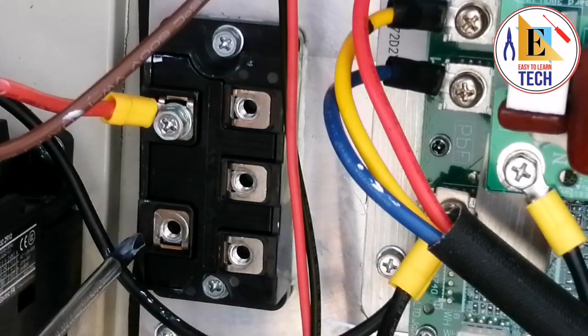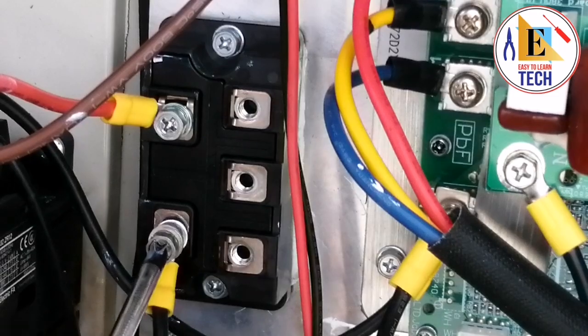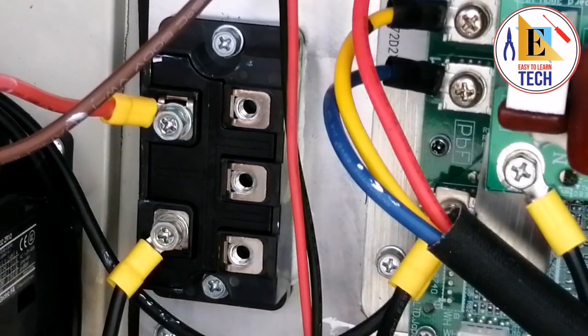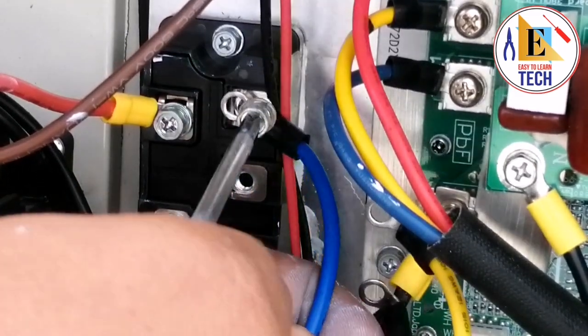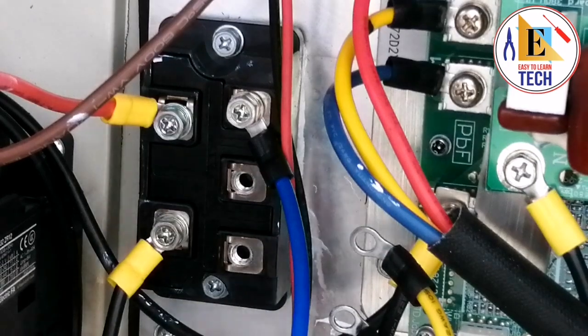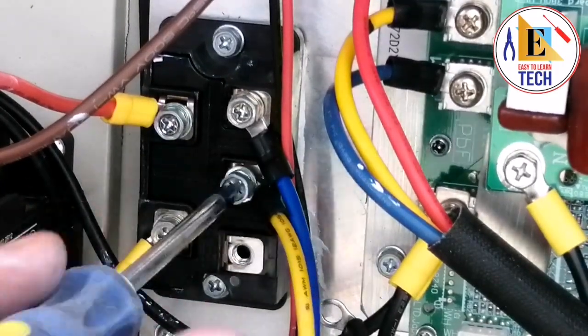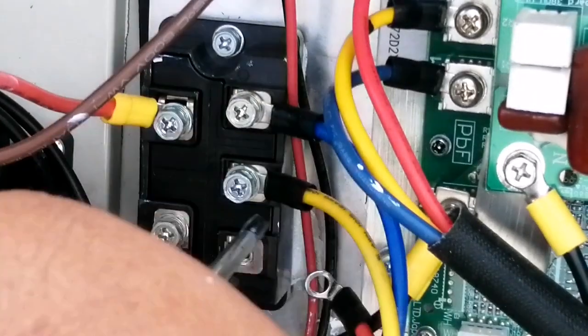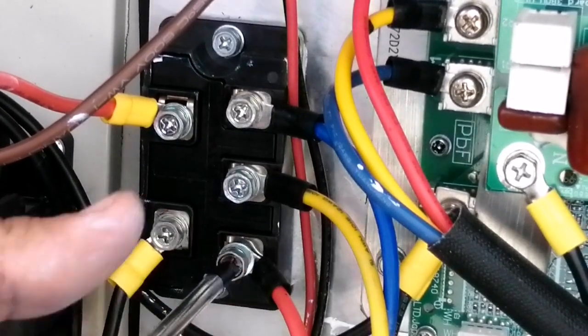You can see on the back side there is a plus sign and here is the minus sign. We have fixed the positive — now we have to fix the negative one which is going to the capacitor. Tighten it properly, we should not keep it loose. Here is our R, Y, B — let's connect the blue wire. We have to connect all the wires for the three-phase and DC current in the same way as we removed them. Don't change the sequence of the phase, keep it as it is. Blue and yellow have been connected. Now red — red is also connected.